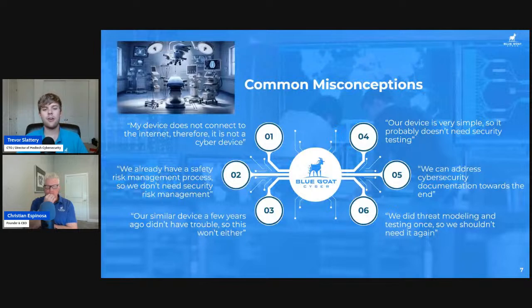However, there are still going to be security considerations. You still should have security requirements. You need to have static testing, fuzz testing. You need to have penetration testing against the product and all of the documentation to go along with your risk management.